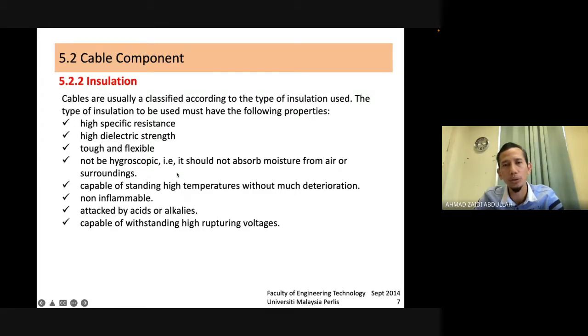And it should not absorb moisture from air or surrounding. And then it also must be capable of standing high temperature, and then not inflammable, attacked by acid or alkali, and capable of withstanding high rupturing voltage. So these are some criteria that normally we check during the selection of the type of insulation for our cable.